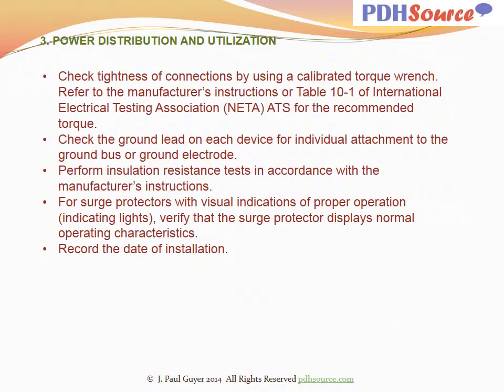Check tightness of connections by using a calibrated torque wrench. Refer to the manufacturer's instructions or Table 10.1 of the International Electrical Testing Association, NETA ATS, for the recommended torque. Check the ground lead on each device for individual attachment to the ground bus or ground electrode. Perform insulation resistance tests in accordance with the manufacturer's instructions. For surge protectors with visual indications of proper operation, indicating lights, verify that the surge protector displays normal operating characteristics and record the date of installation.